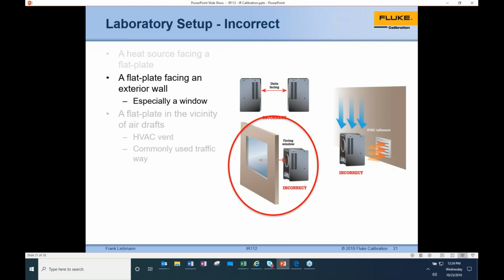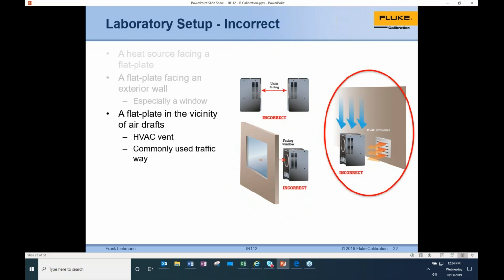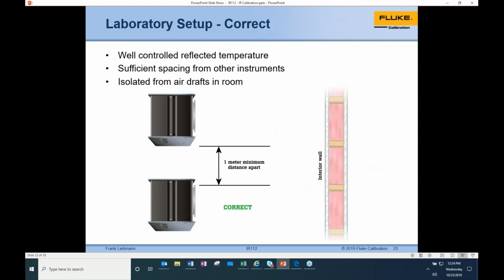Again, windows - you can actually get reflected energy, so you want to avoid those. And I've talked a couple of times too about getting too close to your HVAC type setups. We've actually got a lab down the road from us we worked with, and they had to put a downdraft and updraft, one in each corner, to pull the air in a specific direction through their lab to help equilibrate it. So if you're using multiple units, it's recommended to keep them fairly far apart - 1 meter is about what we recommend, a few feet - and then isolate as much as we can from drafts in the room. An interior wall helps as well, because you're going to reduce any chance of emitting large or radiated energy from, say, a window or something else.